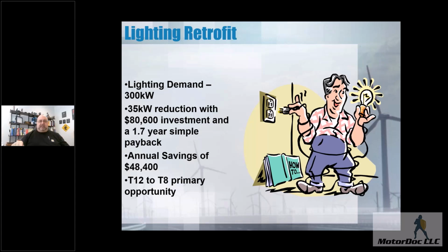And so when they did a lighting retrofit from T8s to LED, we actually noticed their energy consumption in the same conditions went up 1.5% due to harmonics. So lighting demand, I'm sorry, that's in this case.